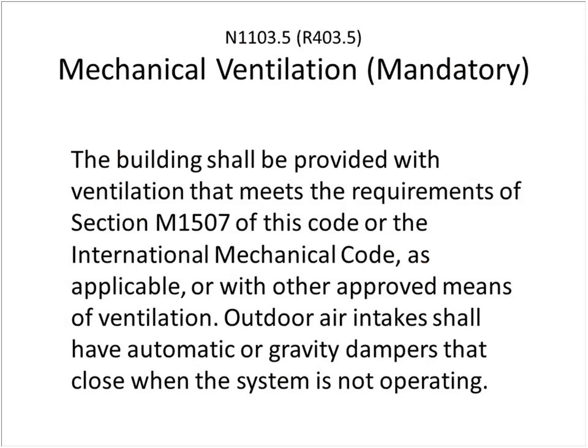Tomorrow we're going to have Jeff from Panasonic come in, and he's going to talk about mechanical ventilation options. I'm just going to kind of gloss over this because Jeff is going to cover the options in detail. Just be aware that mechanical ventilation is required in all homes, residential construction, and the mechanical ventilation then needs to be set for the required number of air changes per hour based on the size of the home and the number of bedrooms. So there's section M1507 of the code, mechanical code requires it, and it's also in the residential energy code.